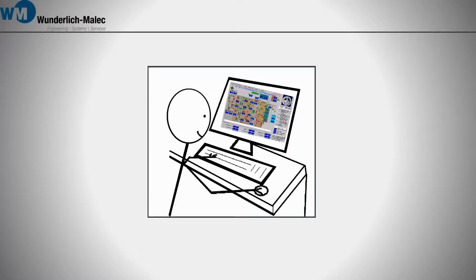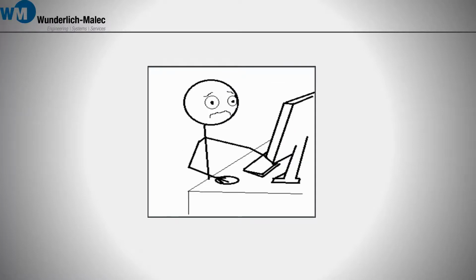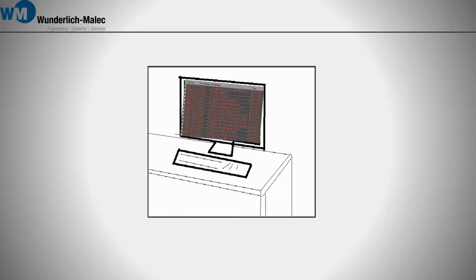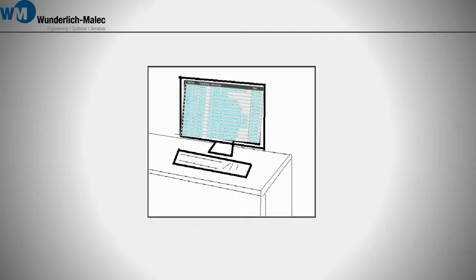Here is an operator checking a traditional SCADA screen. There appears to be a lot of detail, but very little information on how well the system is running. The operator must click through a number of screens to check trends and see all the equipment that is running. Then, a slew of alarms come in, but they're all red.